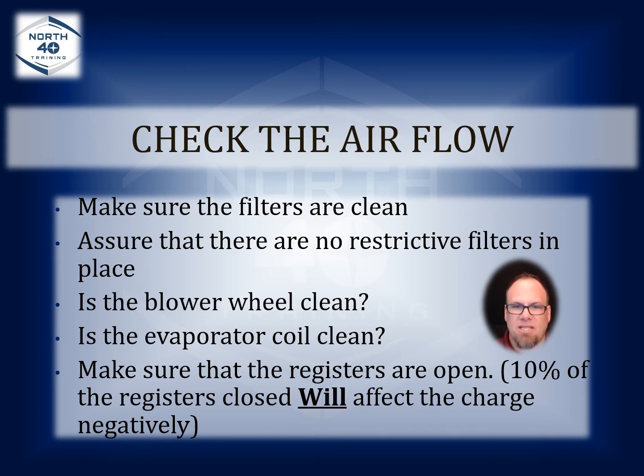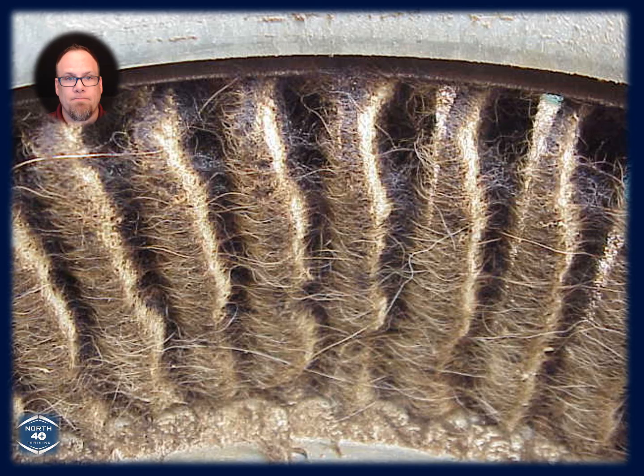The variable speed technology does help in that a little bit, but if you're restricting that airflow by closing the registers, you have unintended consequences of doing that with a variable speed blower, because once you start restricting that, the amp draw goes up and it starts to cost you some more money. And that's originally why you got that variable speed blower in the first place, was one, to push the airflow, of course, but two, to save you money. No, it's only going to save you money if it's in the proper application, and restricting it is definitely not the proper application.